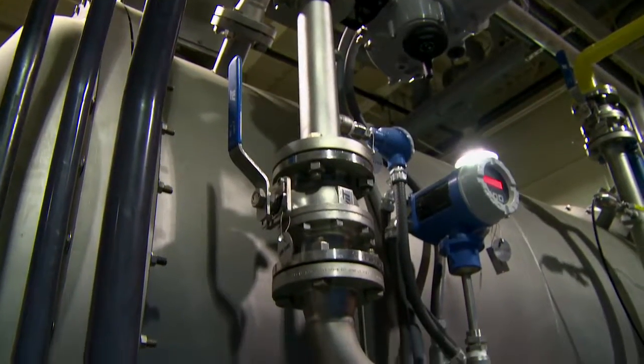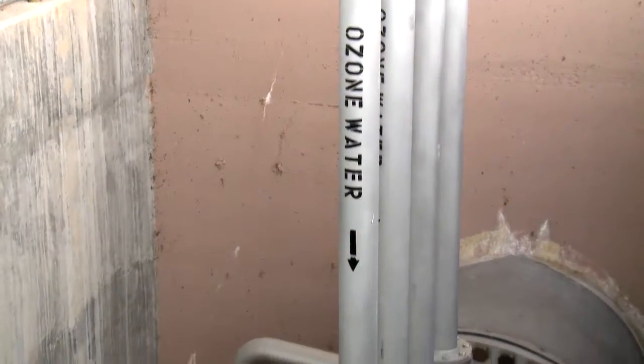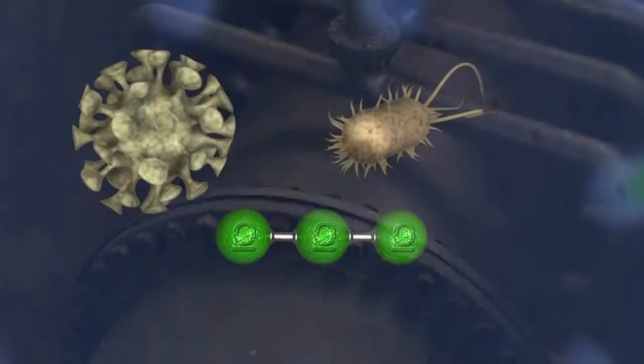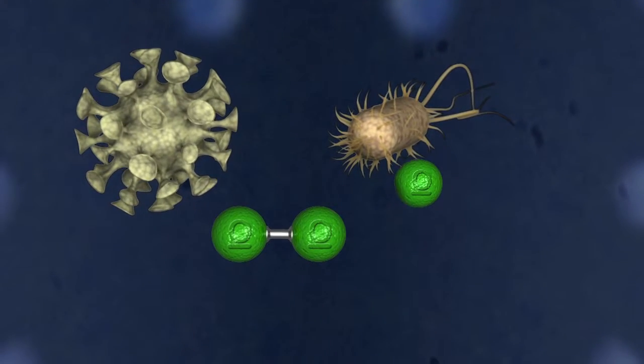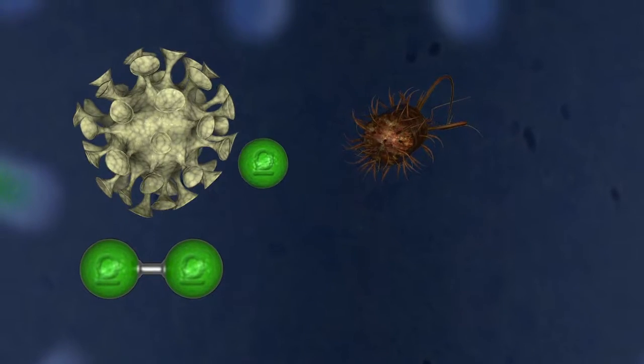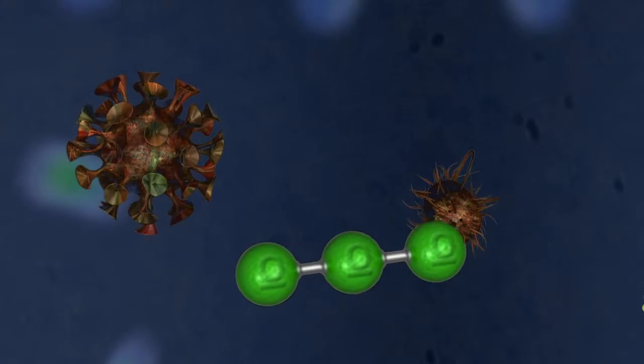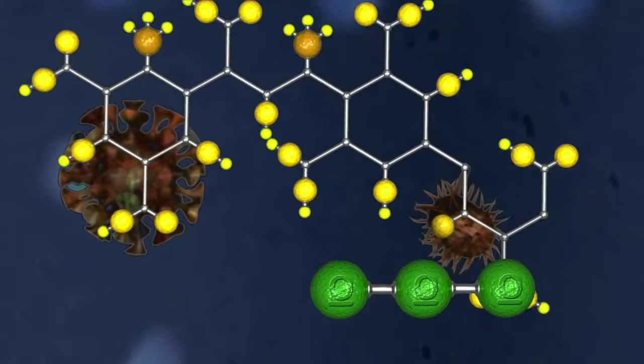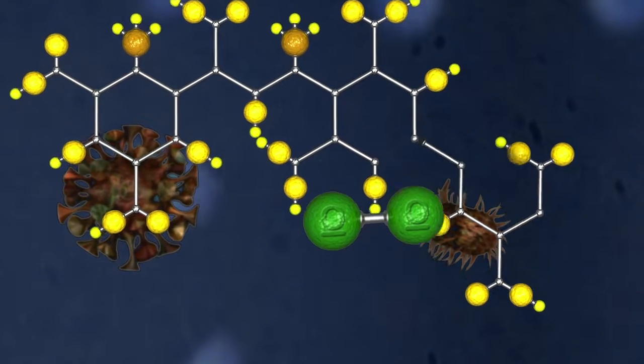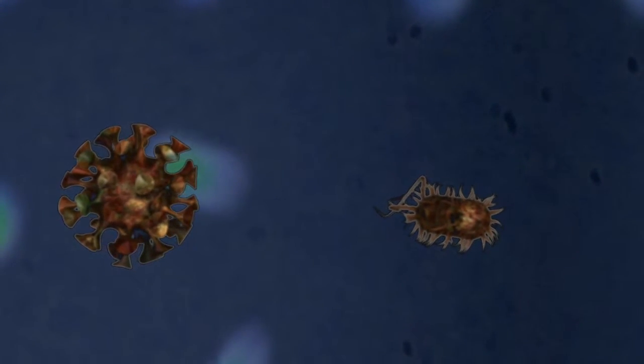We also ozonate it. Ozone is very different and breaks down organics on a molecular basis differently. Ozone is a highly reactive gas. When injected into water, oxygen radicals are formed. These free oxygen atoms work like missiles that attack and destroy bacterial and viral content and help break up complex compounds such as fatty acids, making them more easily consumed in subsequent treatment steps.